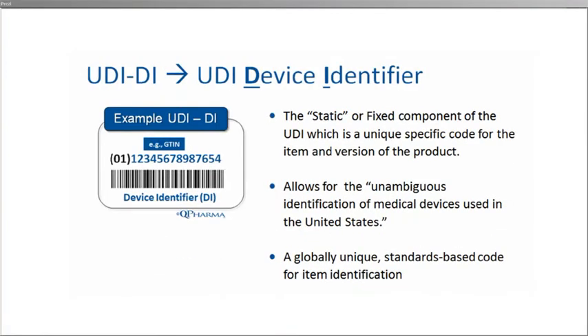The first part of a UDI is the device identifier, known as the UDI-DI. This is the static or fixed part of the UDI. In this example on the left, we show a device identifier, which in this case is a GS1 GTIN, or Global Trade Item Number. GS1 is one of the choices you have for a unique labeling format. The purpose of this component of the UDI is to enable the unambiguous identification of a medical device used in the US, and eventually globally.